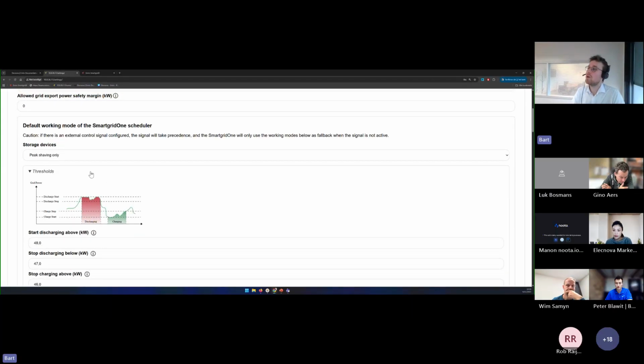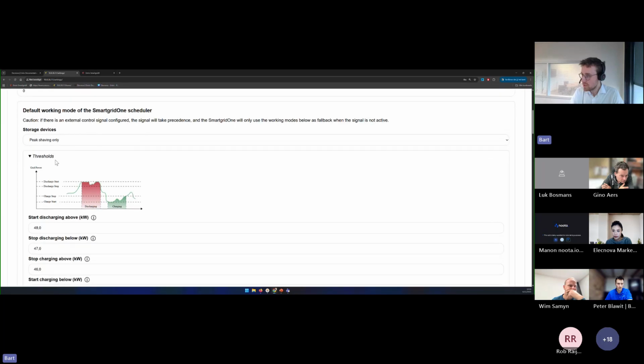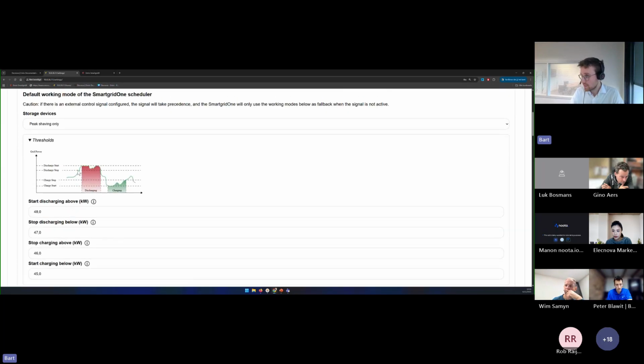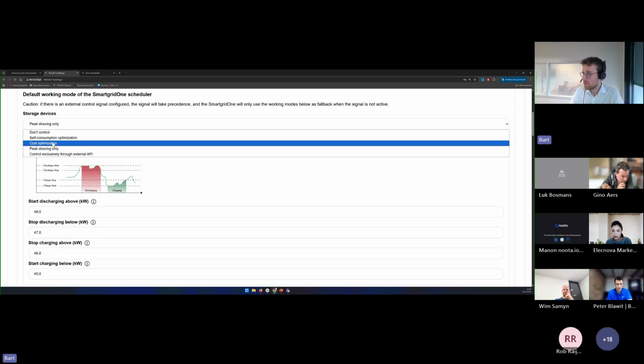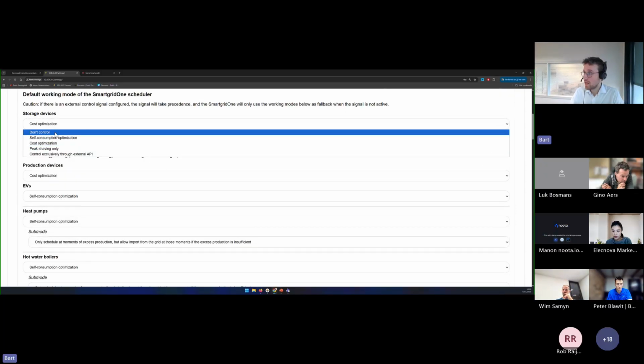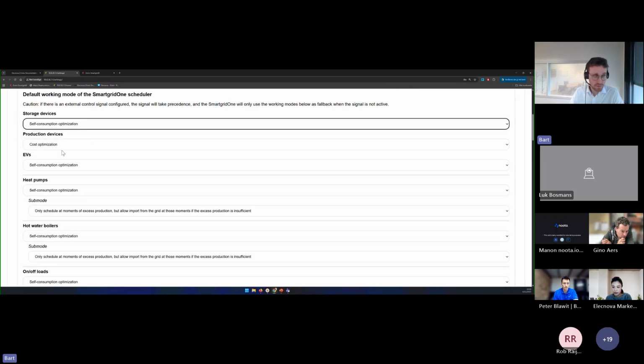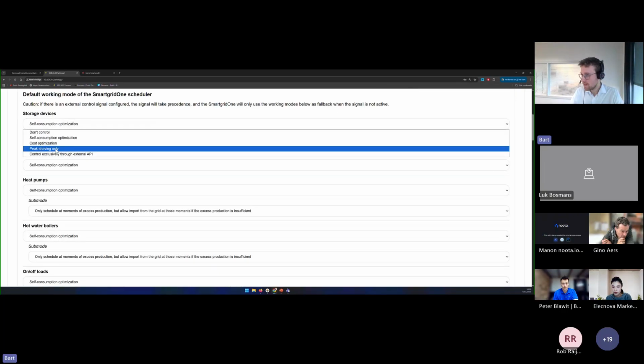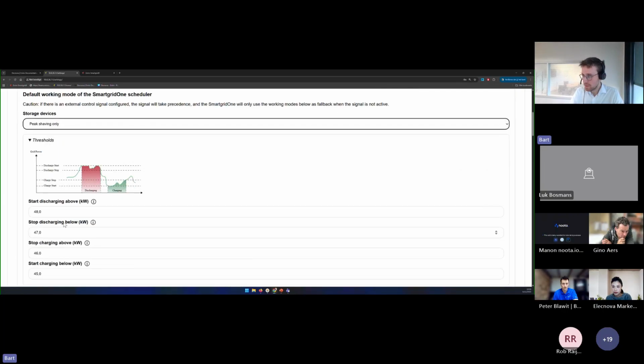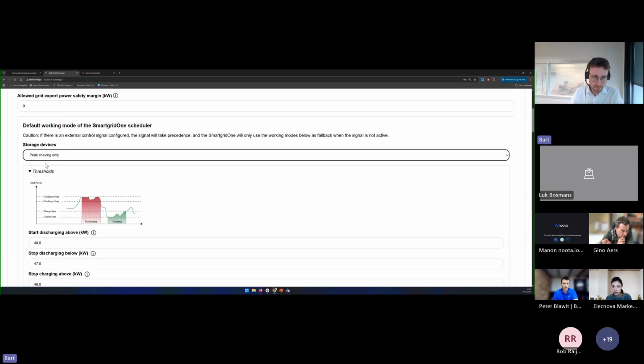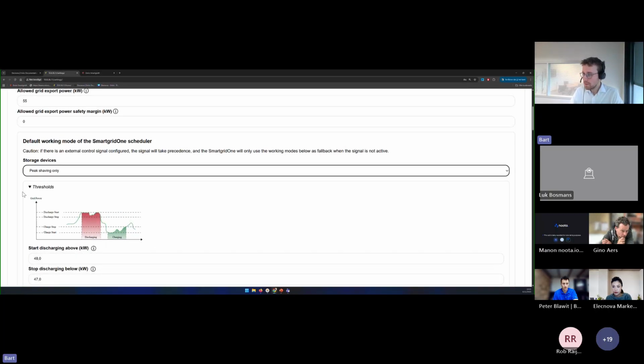For our Elecnova system, as you can see, we have chosen to work with the peak shaving only mode for this particular site, but we could also switch to cost optimization or self-consumption optimization. In our case, we chose peak shaving only mode, but this applies only if there is no external signal applied.